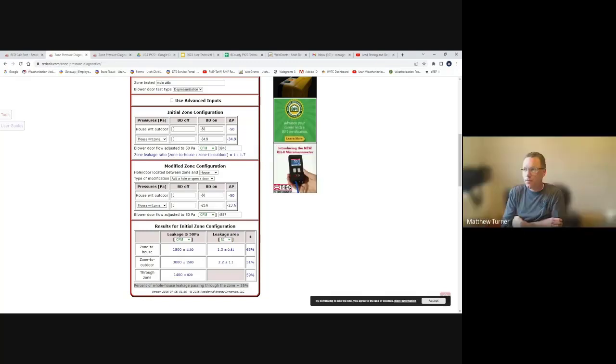So based on a standard audit, how many extra numbers do you have to collect? Just two, because you already collect your blower door and your zonal into your attic. I'd like to make this test required in the near future, so I want to ask you guys to go out and start practicing this now. All we're asking is, once you've set up your blower door, open the attic and measure the other two measurements: get your blower door and get your zonal once your attic's open.